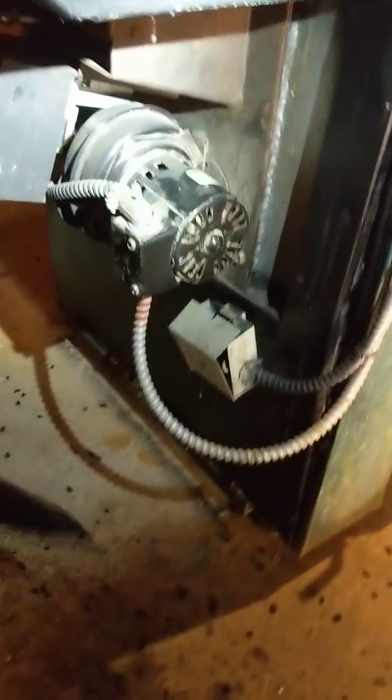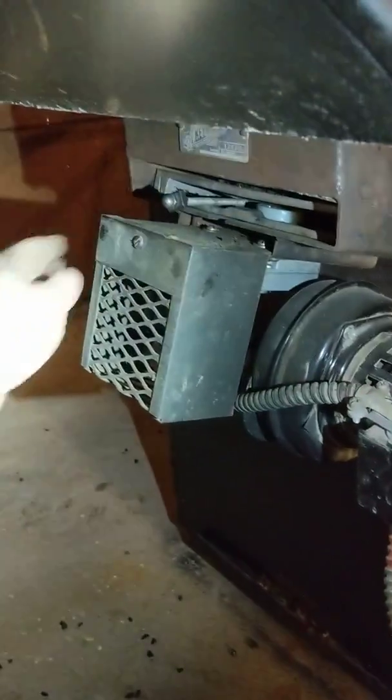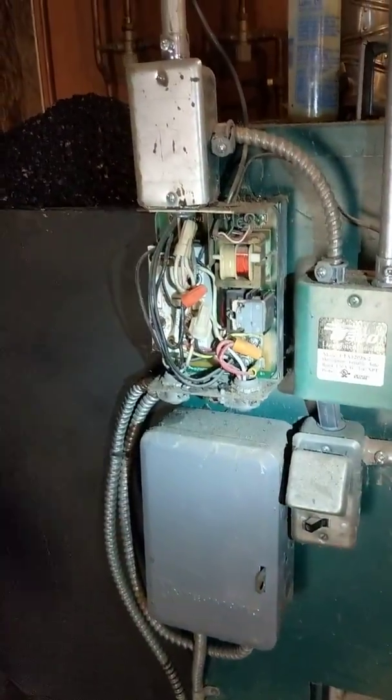At that point in time, if we look down here — this is our blower motor, that's our motor that blows air in for combustion. And this is our pusher setup, it's on a little cam in there. That device moves up and down, pushing coal into the fire. The pusher motor will cycle on and off on a timer once we get over a certain temperature.